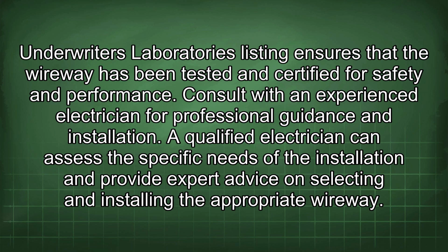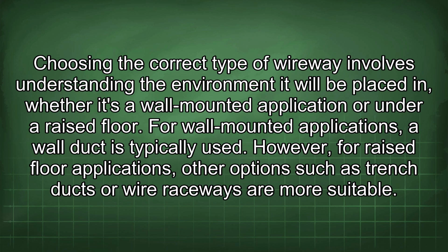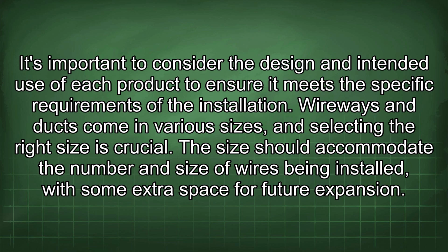Consult with an experienced electrician for professional guidance and installation. A qualified electrician can assess the specific needs of the installation and provide expert advice on selecting and installing the appropriate wireway. Choosing the correct type of wireway involves understanding the environment it will be placed in, whether it's a wall-mounted application or under a raised floor. For wall-mounted applications, a wall duct is typically used. However, for raised floor applications, other options such as trench ducts or wire raceways are more suitable. It's important to consider the design and intended use of each product to ensure it meets the specific requirements of the installation.